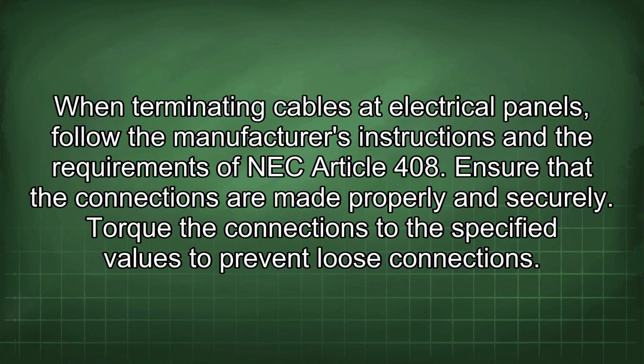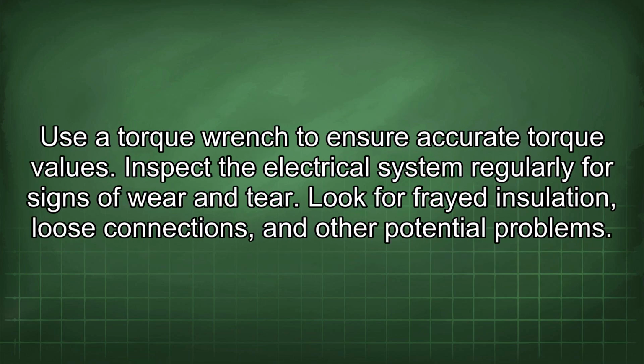When terminating cables at electrical panels, follow the manufacturer's instructions and the requirements of NEC Article 408. Ensure that the connections are made properly and securely. Torque the connections to the specified values to prevent loose connections. Use a torque wrench to ensure accurate torque values.